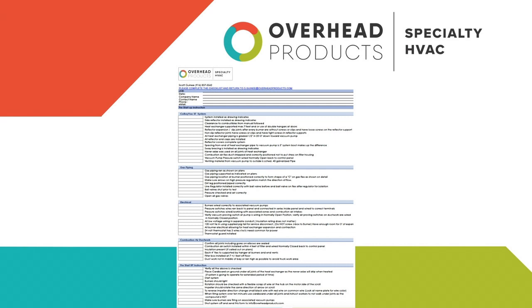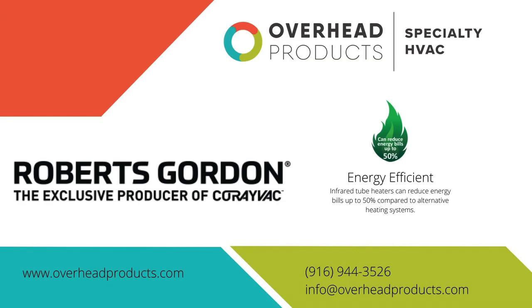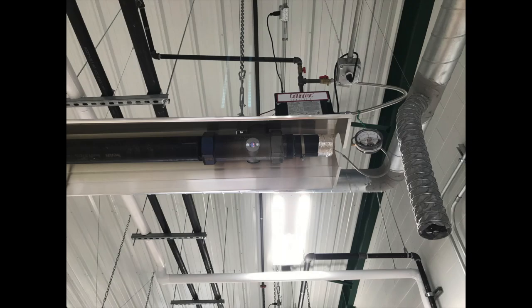The super and the installing contractor should go through this complete list. This list should be sent to Overhead Products. At that time, Overhead Products will work with the superintendent on site to schedule the testing and commissioning of the system. The contractor can start the system up by jumping each stat in each zone to ensure that the burners come on after 45 seconds with respective pumps.